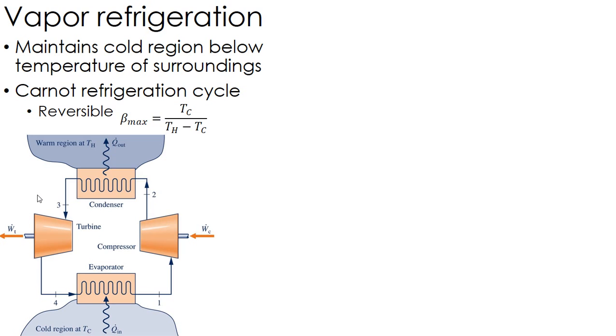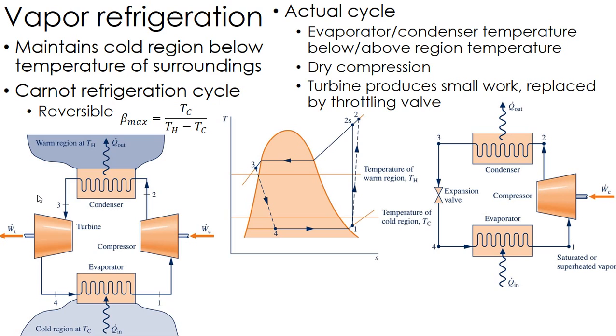Now in actual thing, there's three main differences. First thing is that I can't actually have the refrigerator, the refrigerant temperature the same as the refrigerator temperature. For instance, if I want the refrigerator at 35 degrees, I actually have to have the refrigerant below the 35 degrees in order to get that heat transfer. Same thing goes on the coil on the back of the fridge. That has to be above room temperature to actually get that heat flow. So there's some performance issues with that, that I need that temperature change in order to get heat transfer.